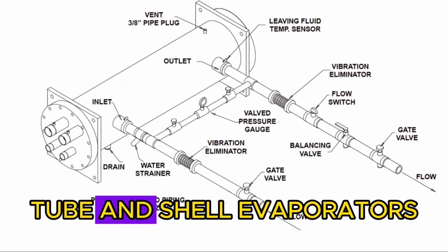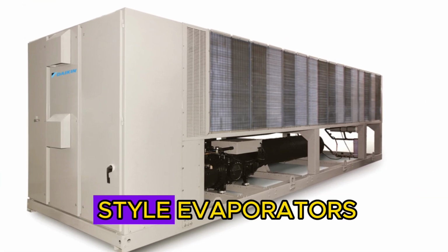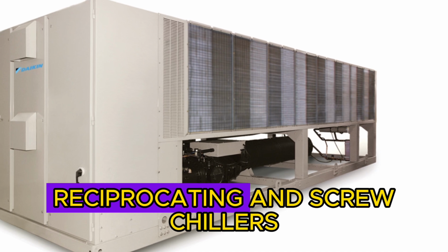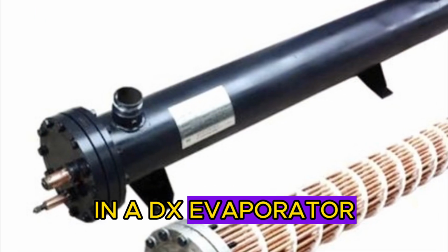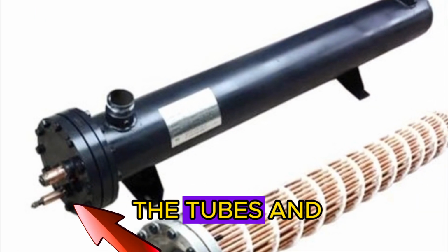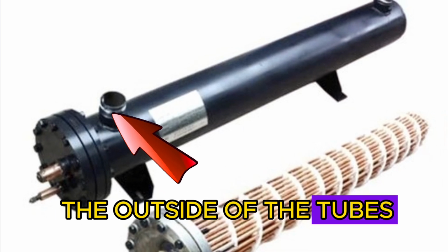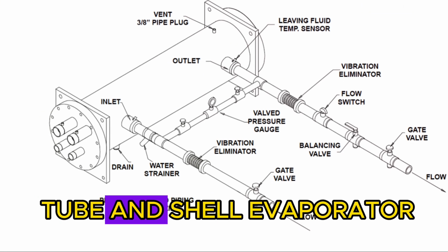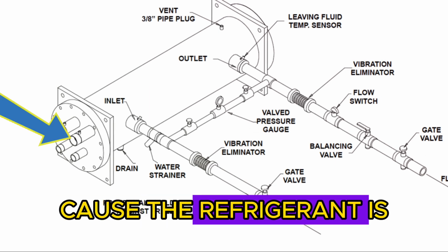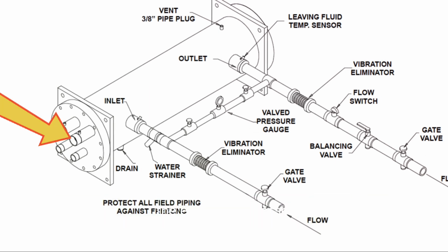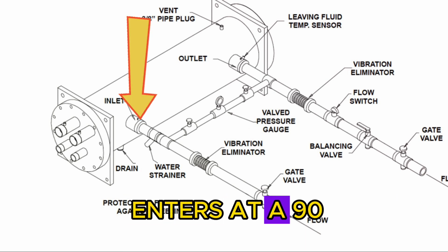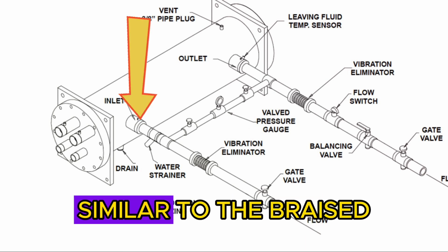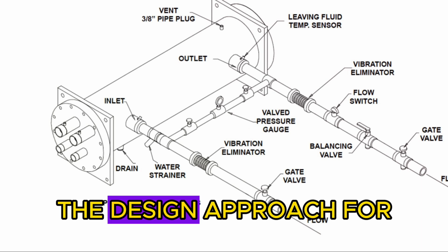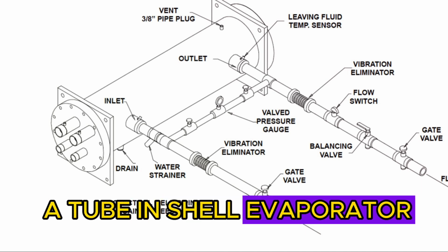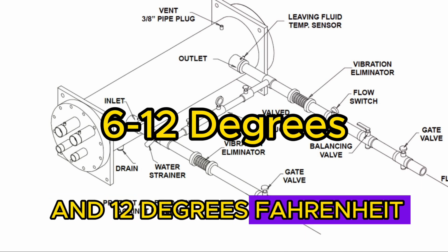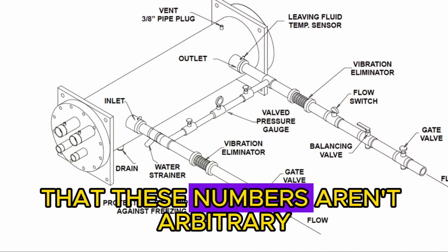Direct expansion tube and shell evaporators. DX tube and shell style evaporators are commonly found on reciprocating and screw chillers. In a DX evaporator, the refrigerant flows inside the tubes and the water flows on the outside of the tubes. You can tell if you have a DX tube and shell evaporator because the refrigerant is fed on the end of the evaporator vessel, and the water typically enters at a 90-degree angle. Similar to the brazed plate heat exchanger, the design approach for a tube and shell evaporator is also between 6 and 12 degrees Fahrenheit.